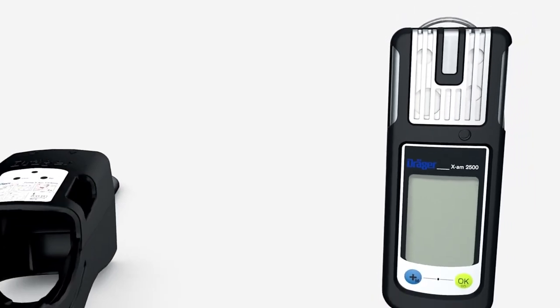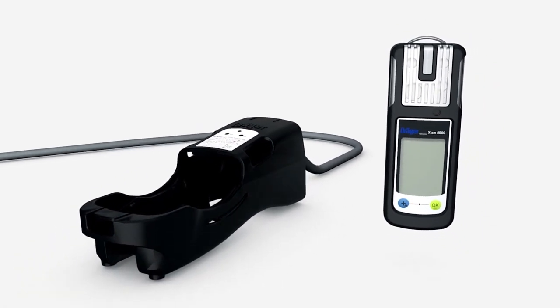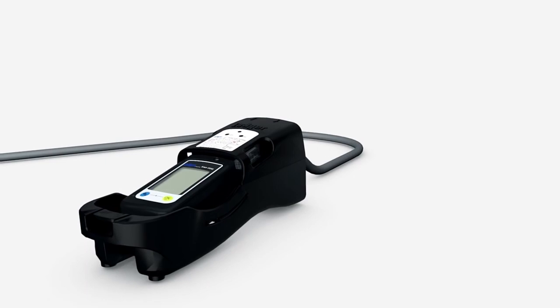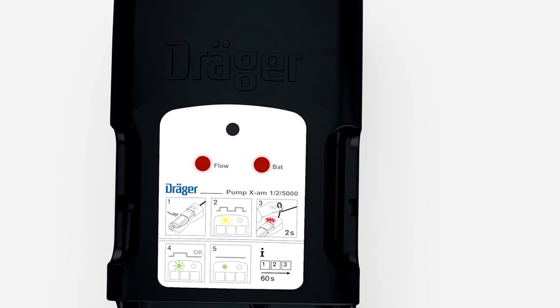The X-am 2500 can also be used with an external pump for atmosphere tests in confined spaces. Place the switched-on device inside the pump and press down until it clicks into place. The LEDs briefly turn green and then red, accompanied by an audible signal. The pump now starts automatically and initializes the flow test. At the same time, the yellow LED flashes and an audible signal can be heard.